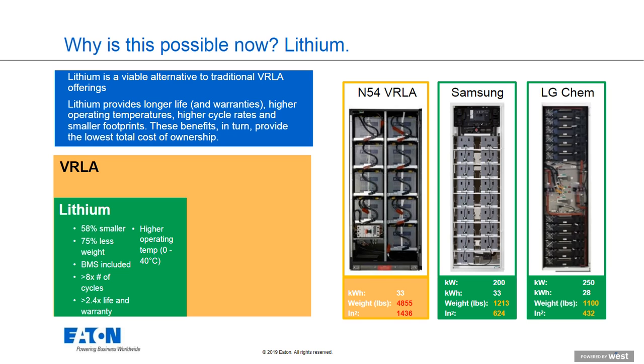On this page, we compare a valve-regulated lead-acid, or VRLA, battery with 33 kilowatt hours of capacity, which translates directly to backup time. The Samsung lithium choice in the middle has the same 33 kilowatt hours of battery backup time, but weight is down to 1,200 pounds from 4,800 pounds for the traditional UPS battery, and square inches goes from 1,400 down to 600. The LG Chem solution on the right is a bit smaller in capacity, but even smaller in terms of weight and size benefit.